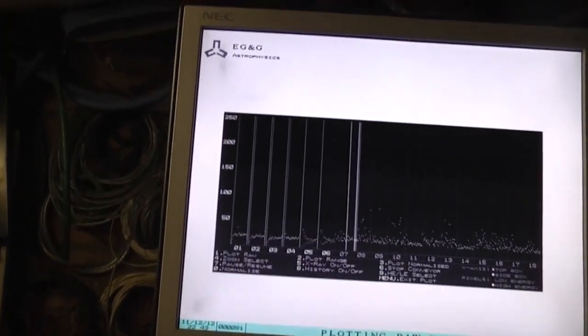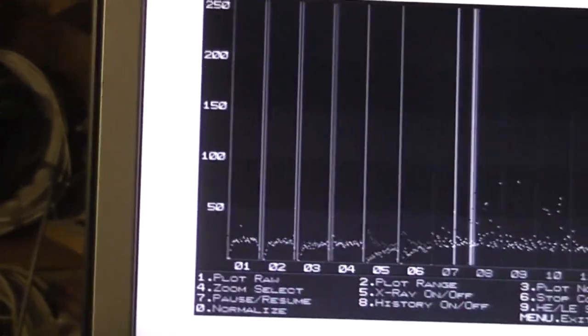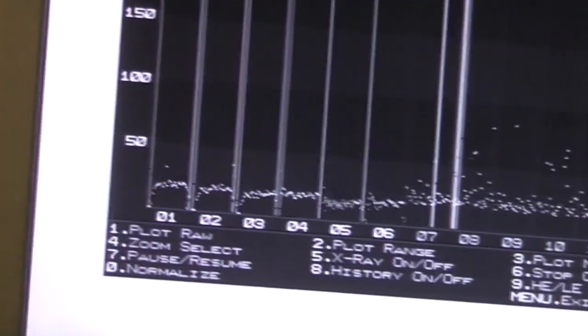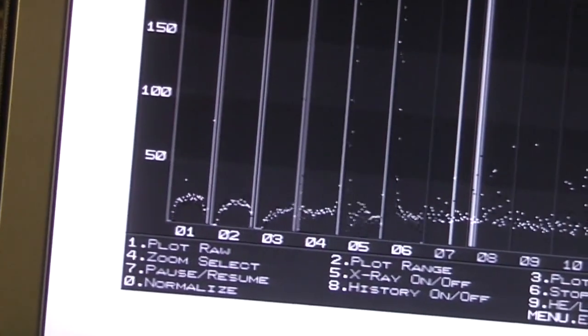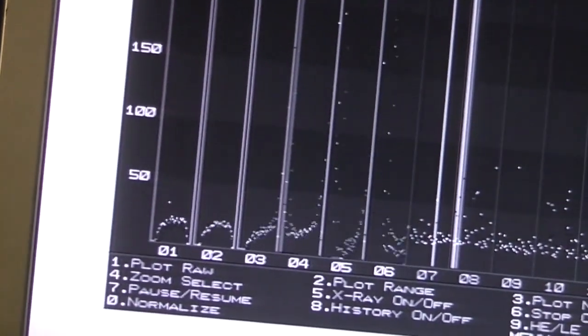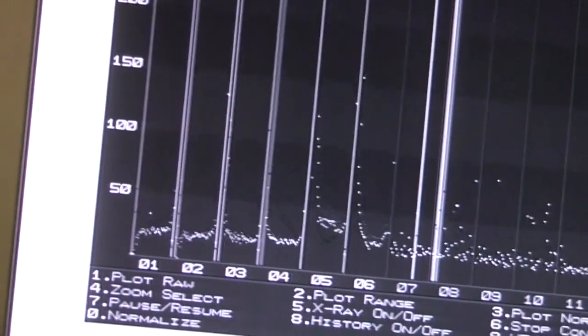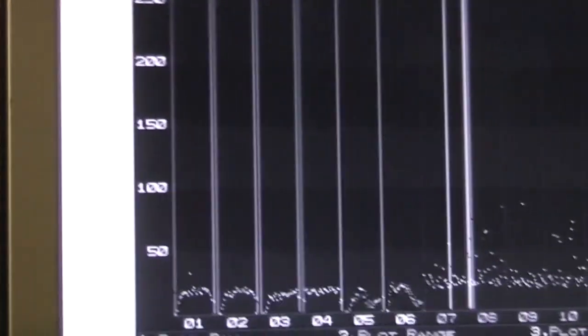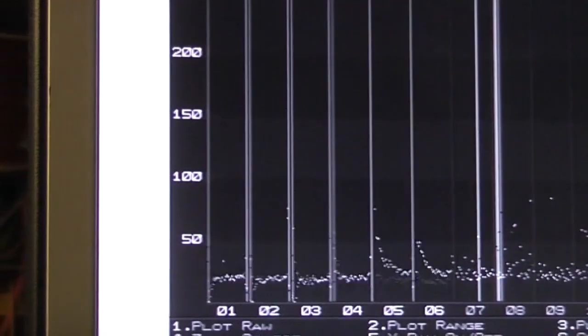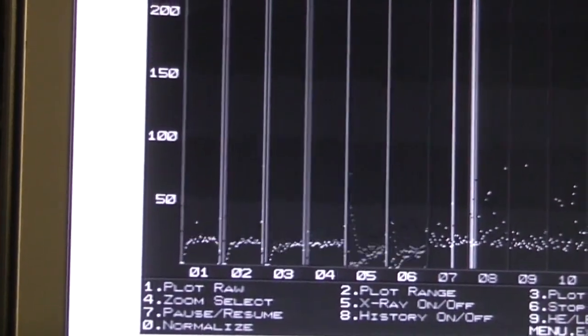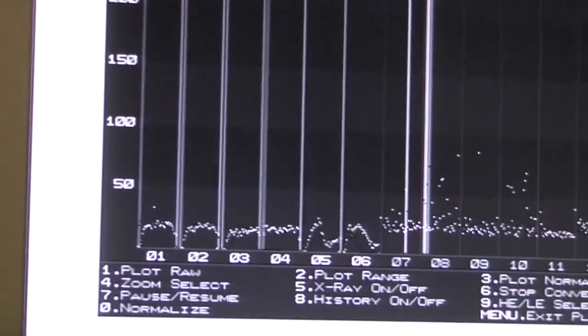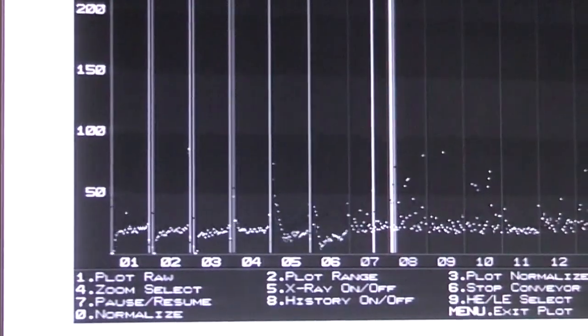Right, I've just pulled the back off and put it back into this plot mode. Now, it's interesting, when it went into this mode we've got these great big spikes. I think these correspond to where the light's going through these slots and hitting the photodiodes, producing a very high reading. So I'm wondering if these lines are indicating ones that are beyond the bad diode threshold. If I move the light around, you can see all the back box detectors picking the signal up. I'm wondering if those peaks are indicating the things that are outside of its nominal bad diode threshold when it starts up. So I'll have a quick play with that threshold and see if that makes any difference.